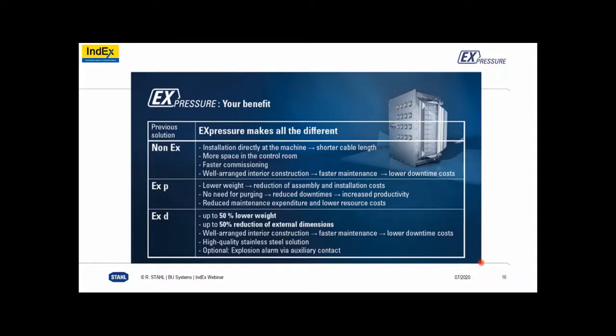So when people were asking what the advantages of ExPressure over EXP are, I will state that with EXP, you have to ensure that you have clean, dry, high quality air or nitrogen. That is not always possible in remote locations, dirty locations, high humidity locations. And when it does fail, you're looking at 5 volume changes. You could be looking at 30 minutes to an hour to restart that EXP cabinet. EXP also has problems with temperatures. When it overheats, that happens quite a bit.